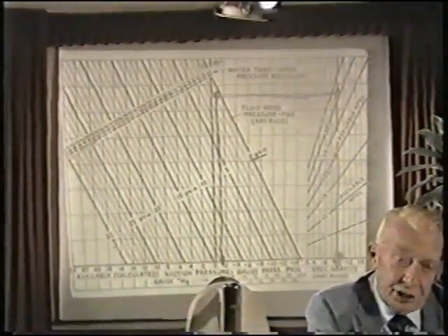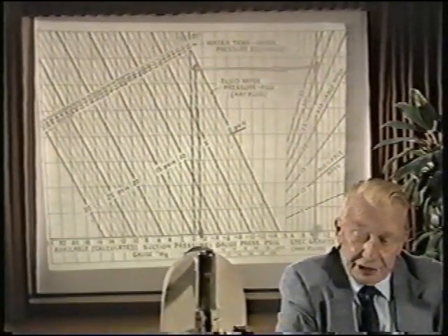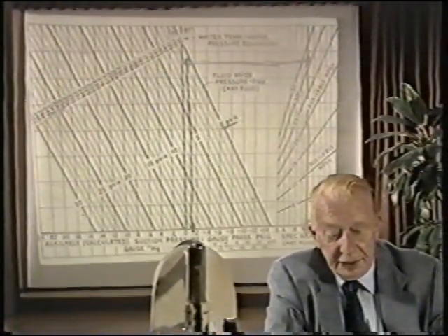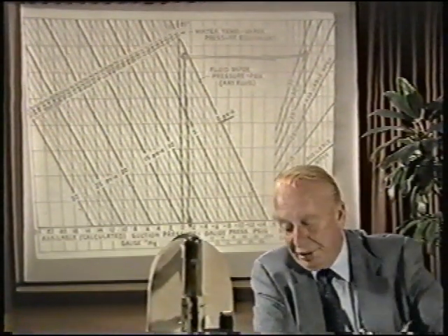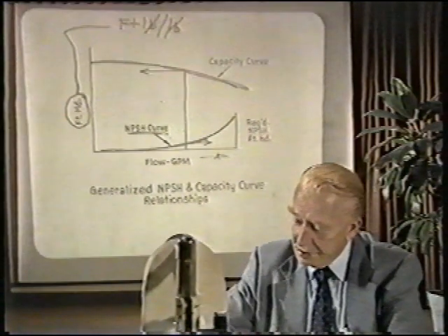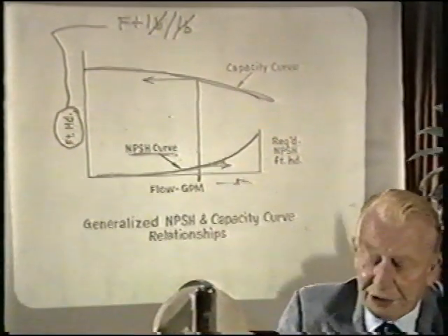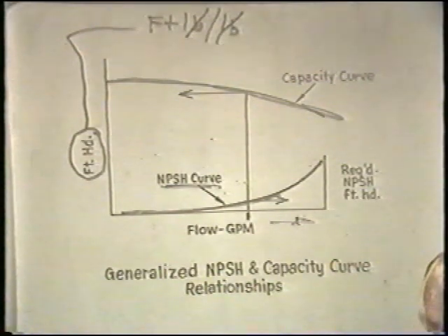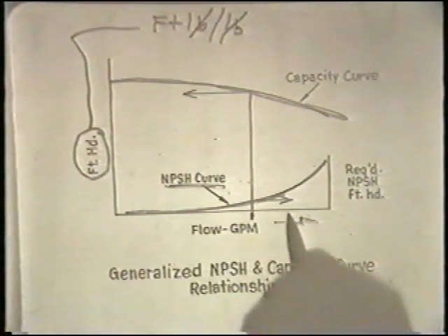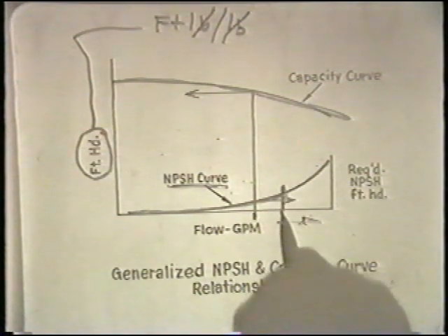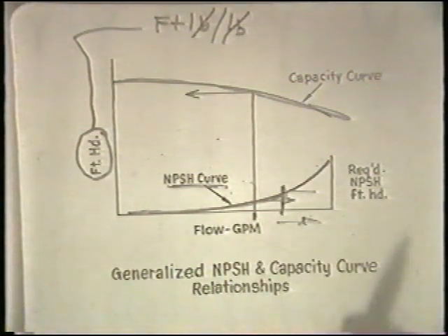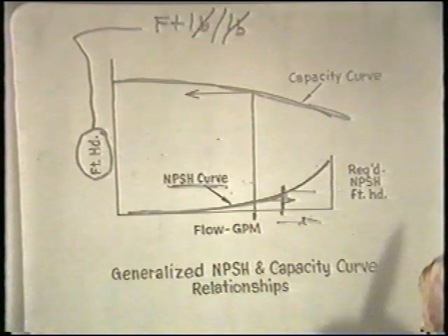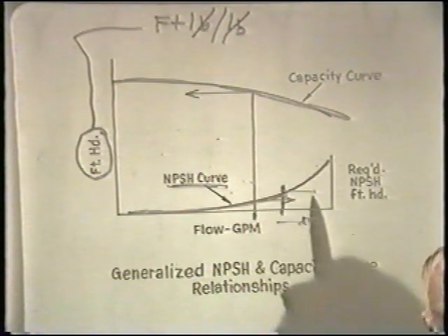We should provide, of course, some safety factor in terms of selection, because if the pump does deviate from the selected point, that might be illustrated here. We have a selection point at this point, but as will be illustrated later in terms of power application, if our pumping point is actually farther out in the curve, we will, of course, establish a higher required NPSH and could run into difficulties because of slippage of the pumping point.